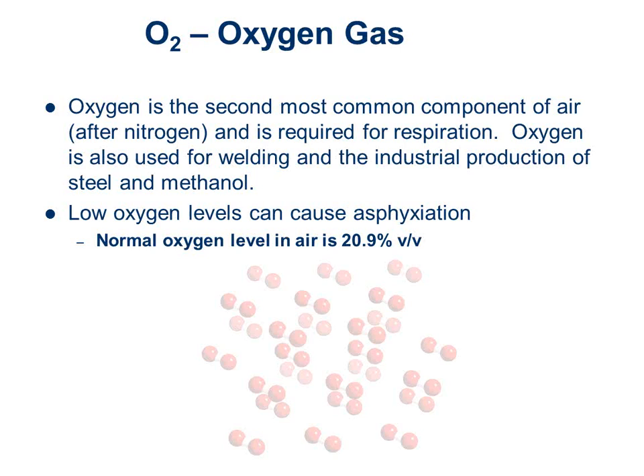We also put oxygen sensors a lot in fire stations, because fire stations store oxygen tanks. In those cases, I want to measure oxygen to see if there's too much, because that means some of my tanks are leaking, and if I leak a lot of oxygen, it's more likely I can have a combustion incident. Hopefully in a fire department it doesn't happen because those guys should be smart enough not to smoke by the oxygen tank, but that doesn't mean we don't want the belt-and-suspenders sensors. In fact, in fire stations, the more sensors you give those guys, the happier they are - they want to over-monitor everything because that's just how they're wired. So we can monitor oxygen for too little or too much, depending on our concern.